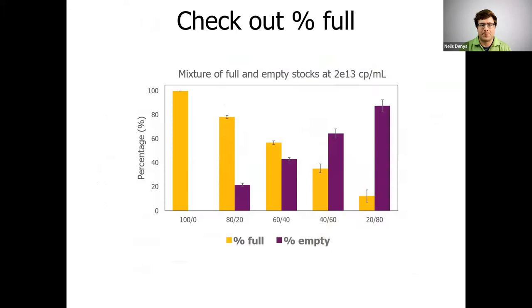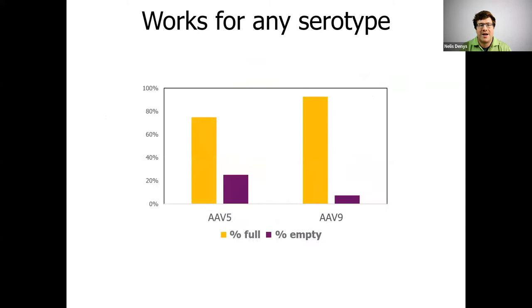Now let's look a bit more into our ability to see percent-full values. We took stocks of empty and full AAV9 and mixed them at different ratios. For each combination — 100% full, 80% full, and so on — Stunner gets a good read on the data, and the percent full and percent empty align well with our expected values. The great thing is the application works for any serotype. You just tell Stunner the basics about which serotype you have and what its DNA payload is, and Stunner will take care of all the heavy calculations.